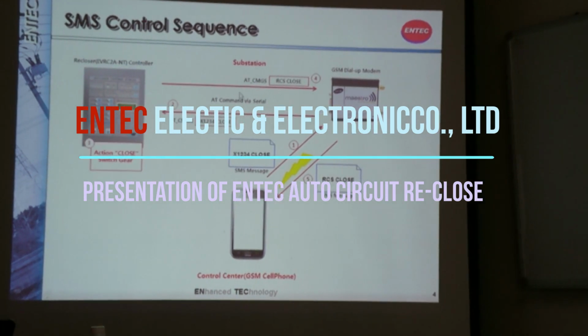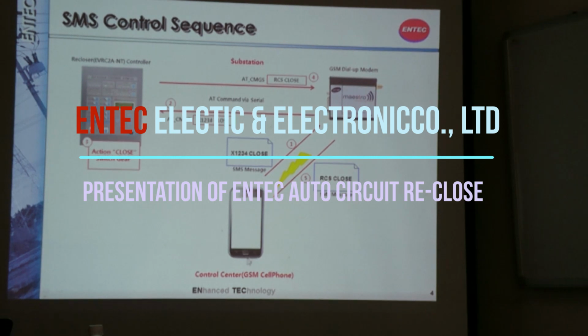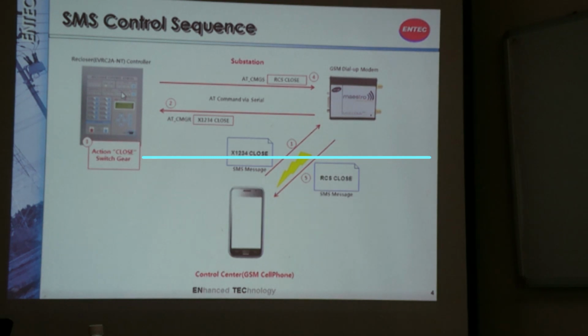So here is the concept. First, when your cell phone gives a command to the modem, it will include the password and the command. Then the modem will send the command to the controller. The controller will operate the switch gear. Then the switch gear will have a status change. In that case, the switch gear will report to the modem that its status has changed to closed, and then the modem will report back to the smartphone that the switch gear is closed.